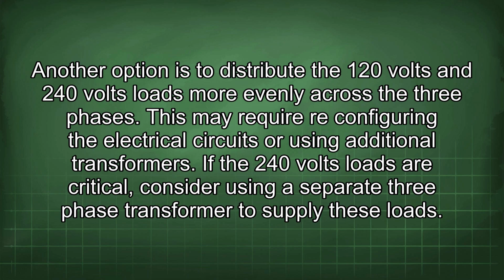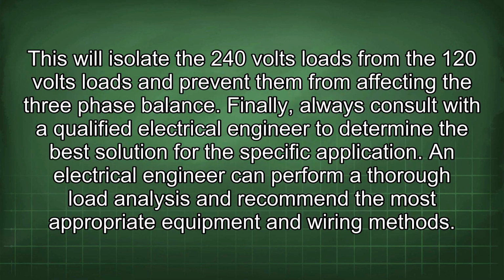If the 240-volt loads are critical, consider using a separate three-phase transformer to supply these loads. This will isolate the 240-volt loads from the 120-volt loads and prevent them from affecting the three-phase balance. Finally, always consult with a qualified electrical engineer to determine the best solution for the specific application. An electrical engineer can perform a thorough load analysis and recommend the most appropriate equipment and wiring methods.